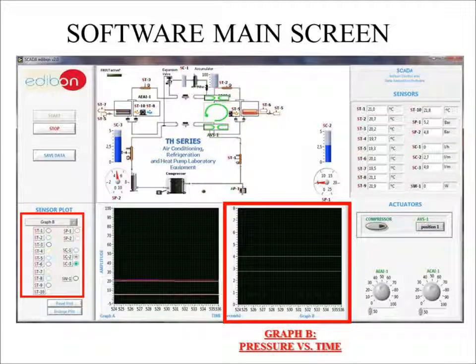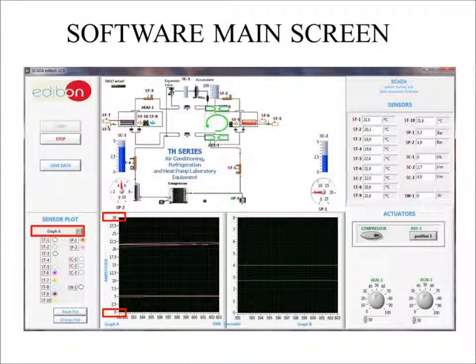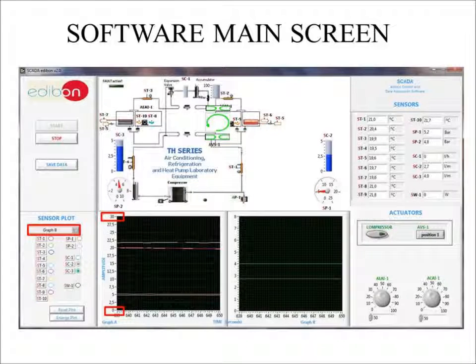Using the drop-down arrow, choose graph B and select SC2 and SC3. This will be the pressure versus time representation. Using the drop-down arrow again, select graph A and change the scale from 100 to 30 and from -5 to 0, simply by clicking on 100 and writing 30 for a better visualization of the graph. Do the same thing for graph B.